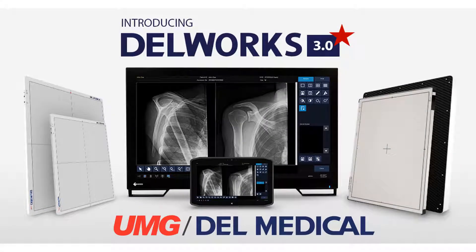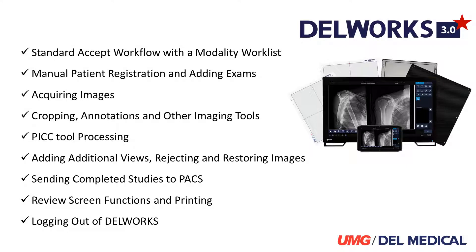This video describes the workflow and features of DelWorks version 3.0. In this video, we will review standard accept workflow with a modality worklist, manual patient registration and adding exams, acquiring images, cropping annotations and other imaging tools, PICC tool processing, adding additional views, rejecting and restoring images, sending completed studies to PACS, review screen functions and printing, and logging out of DelWorks.